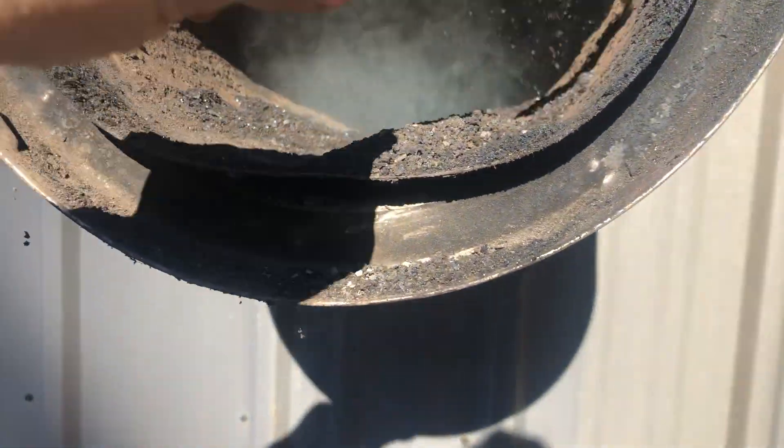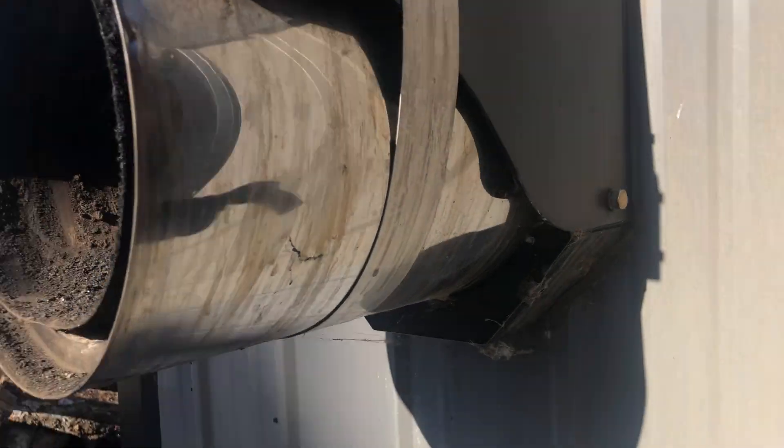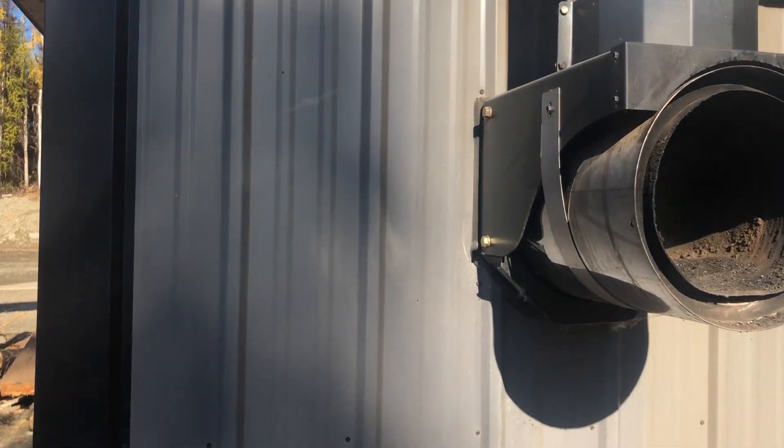I don't know that it's clogged enough to cause the draft issue. The draft issue is that under the box there, behind the garbage can — if you have a Central Boiler, you know what I'm talking about — that thing was completely filled with creosote and completely ruined the gas valve in there, so the gas wouldn't turn on.